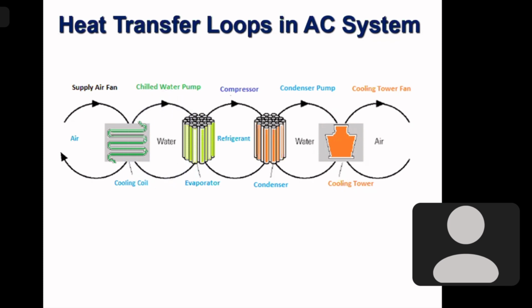So room heat comes from the room by air to the cooling coil, from where it is taken again by the chilled water and goes to the evaporator, which heats up the cold expanded refrigerant gas, and that refrigerant gas becomes hot. We take it back to the compressor, we compress it, it takes further heat from the work done on the refrigerant by the compressor. Then we take the refrigerant to a condenser where we cool it by water. It is a water-cooled system.